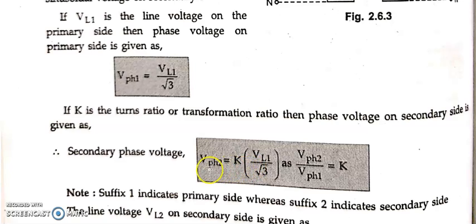Again, if I want to write the phase voltage of the secondary side in terms of the line voltage of the primary side, the formula will be V phase 2 equals K times VL1 by root 3. Otherwise, with the same primary winding, it will be V phase 1 equals VL1 by root 3. Here 2 represents secondary side, 1 represents primary side.